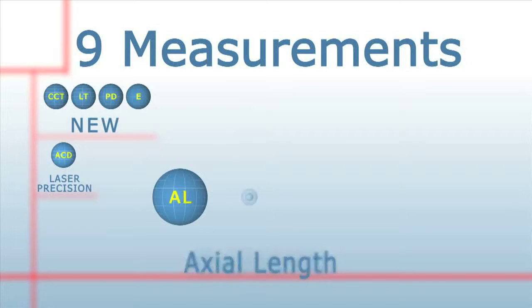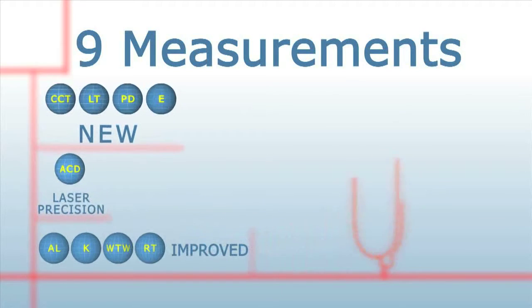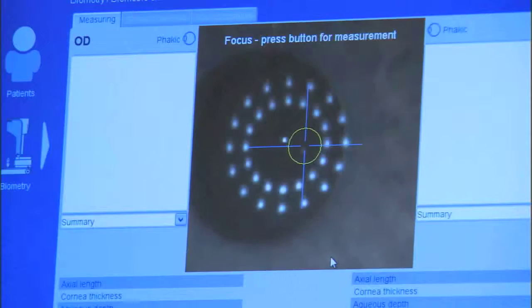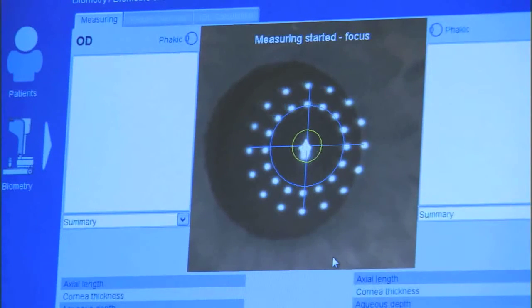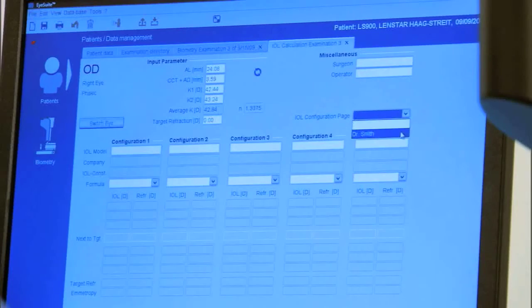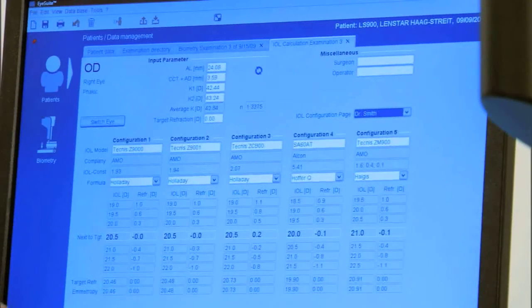Choosing the correct IOL power is a critical step in achieving consistent, perfect outcomes and happy patients. In normal eye lengths, the more simple formulas provide adequate results. In more difficult eyes like hyperopes and myopes, the advanced formulas like the Holladay IOL Consultant become a necessity. LENSTAR includes the basic formulas — SRKT, Holladay One, Haigis, and Hoffer Q. For the Holladay IOL Consultant, LENSTAR can auto-populate the patient data fields, saving you significant time and eliminating the risk and liability of transcription error.